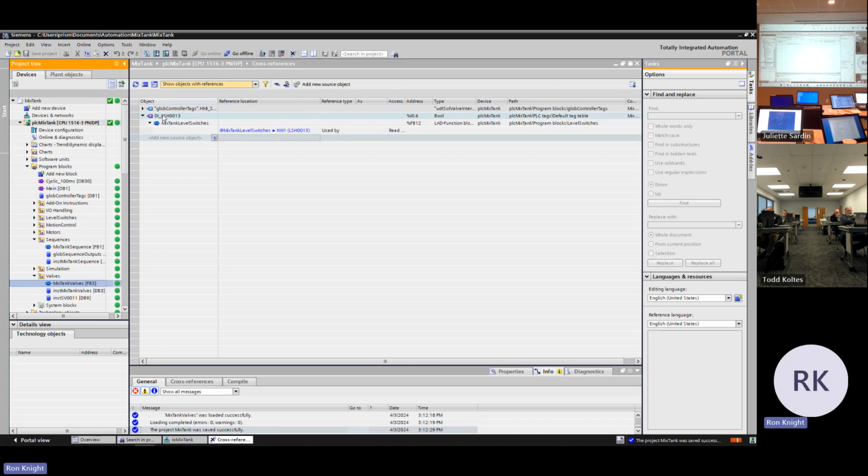Instrumentation. The trend functionality is a great troubleshooting tool where you're trying to figure out, okay, does this cause this? What's the timing on this? Does it always follow that this happens? Or maybe you're tuning a PID loop. It's not a replacement for a trend inside of an HMI or anything. This is a diagnostic tool.